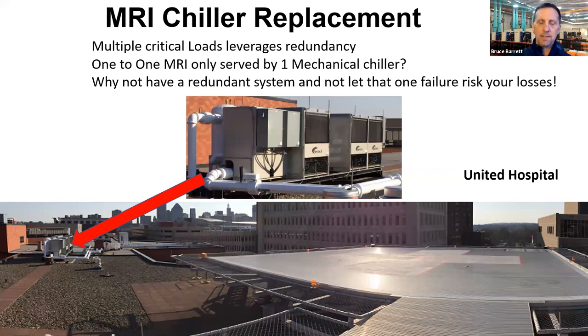It was not an emergency to repair that coil because it was in the cold of winter. The hospital took their time, ordered the parts. When it warmed up outside and the mechanics didn't freeze their hands, they replaced that coil. They never lost capacity. They've estimated their return on investment, even though these chillers cost much more than a replacement, their full return on investment was about 1.5 years for this machine. They've had zero downtime.